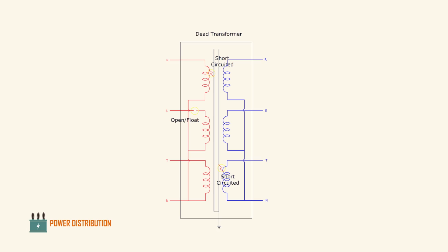To put things in perspective about this dead transformer, we know from our measurement that all the primary and the secondary bushings show a zero reading, except for phase B, which shows some reading, which means probably inside the transformer there is some breakdown on the winding conductor, causing the phase B terminal to float and show some reading.